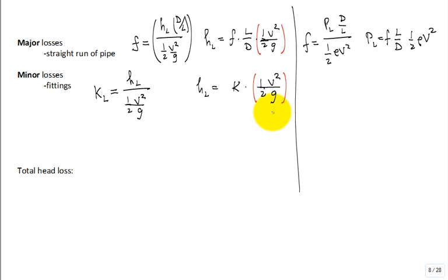So if I just have a straight run of 2-inch pipe, and then next time I have a straight run of 2-inch pipe, but somewhere in the middle of it I put in a ball valve or some other valve that's an obstruction, then it has the same V because it's the same diameter for the fitting as well as for the valve, which is a fitting, as well as the straight run of the pipe. It's the same velocity pressure used in those head loss calculations for the straight run as well as for the loss coefficient for the fitting.